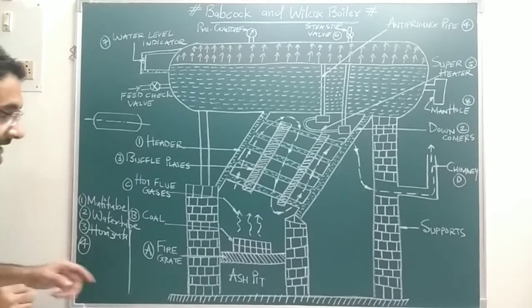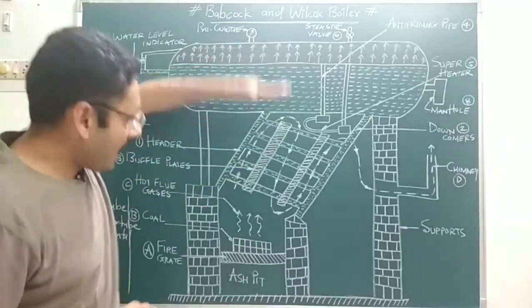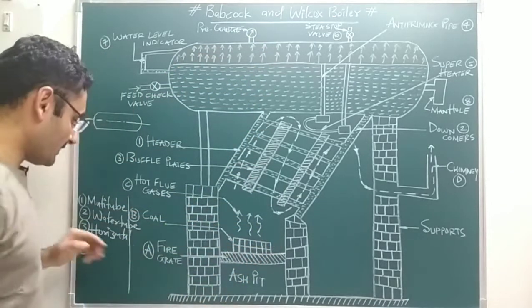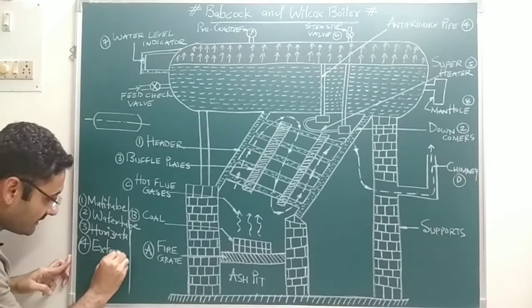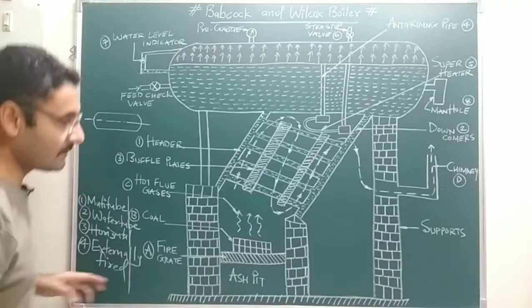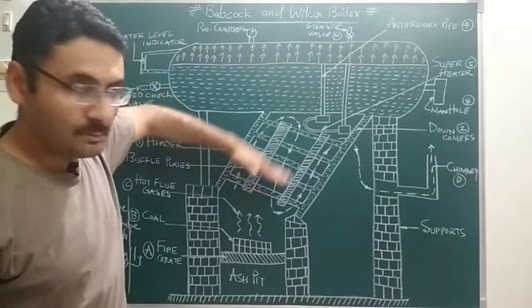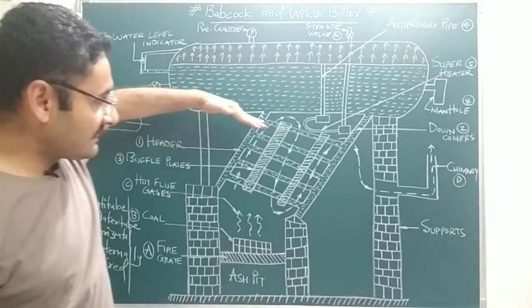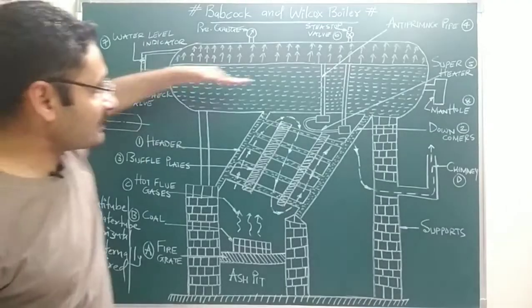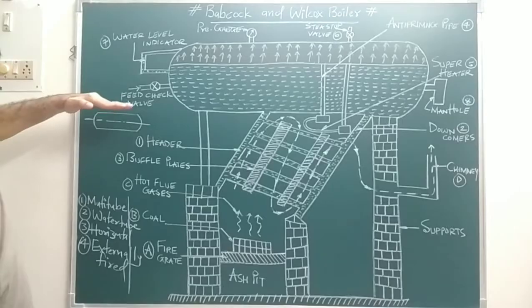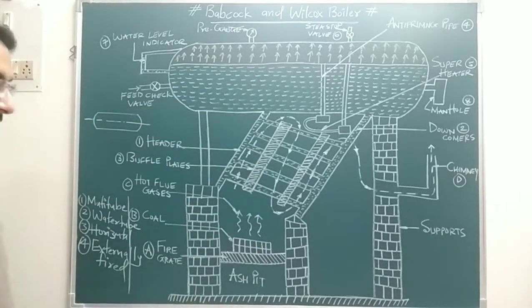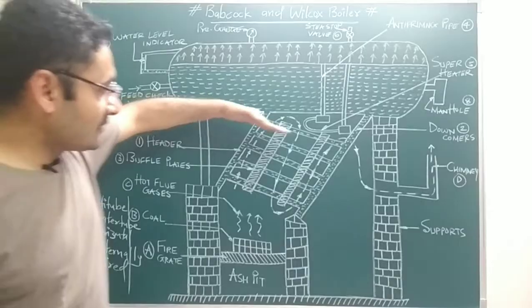The fourth point: combustion of the fuel takes place outside the shell of the boiler, so this boiler is also known as an externally fired boiler. To summarize: multi-tube boiler, water tube boiler, horizontal axis boiler, and externally fired boiler. Additionally, the tubes are inclined at up to 15 degrees so we can take advantage of natural circulation of water.